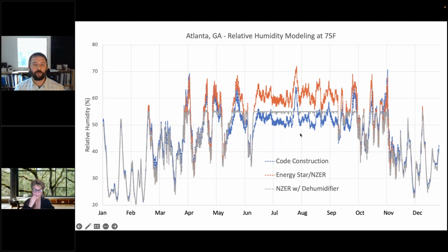So we see that as we advance from code built to above code built programs, that we typically see an increase in interior RH. And this is because typically we're reducing the sensible load at a greater reduction than reducing the latent load.